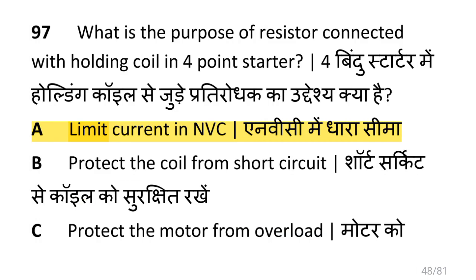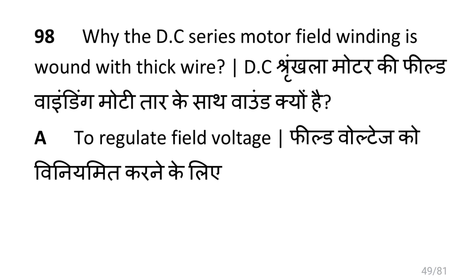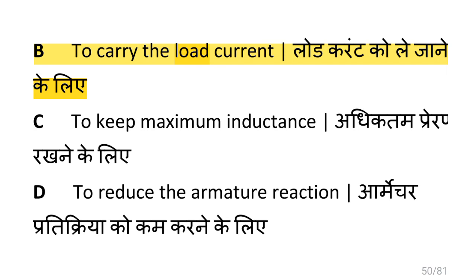What is the purpose of the resistor connected with the holding coil in a 4 point starter? That is to limit the current in the no-volt coil (NVC). Why is the DC series motor field winding wound with thick wire? That is to carry the load current.